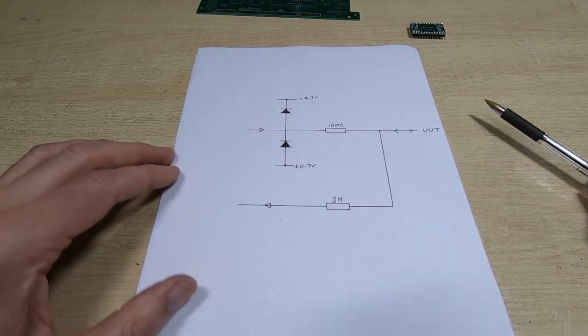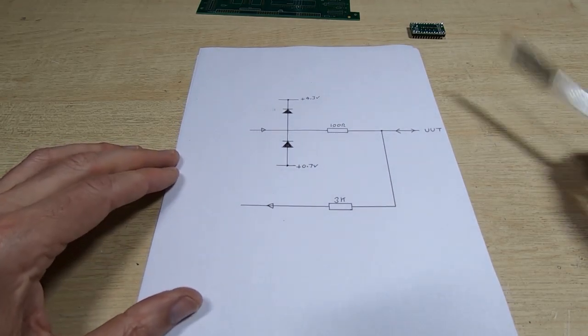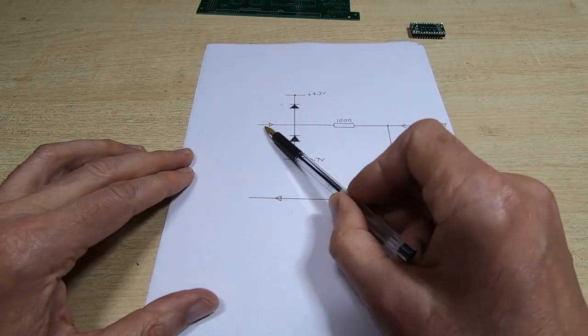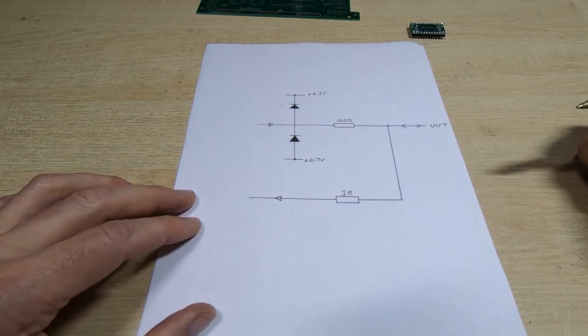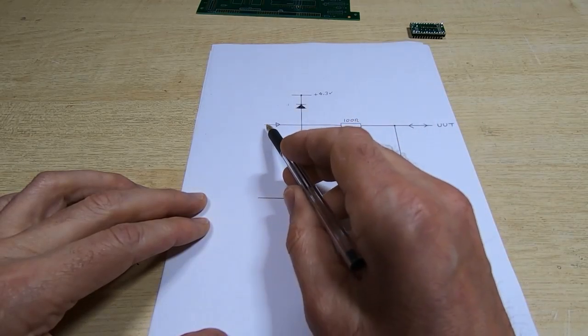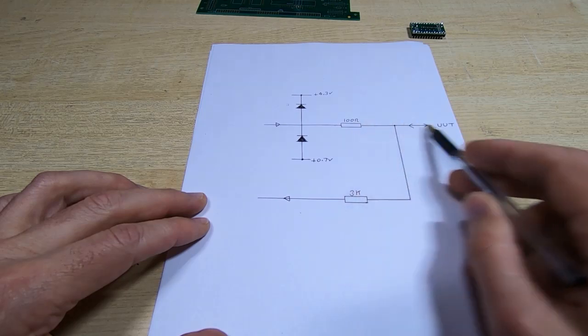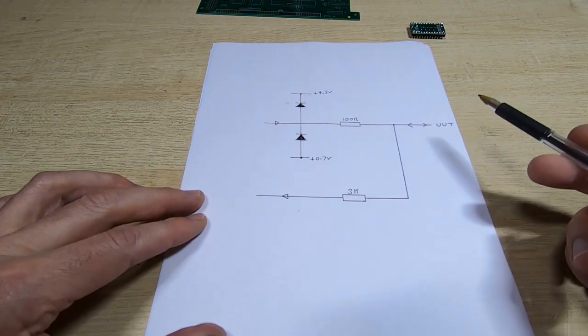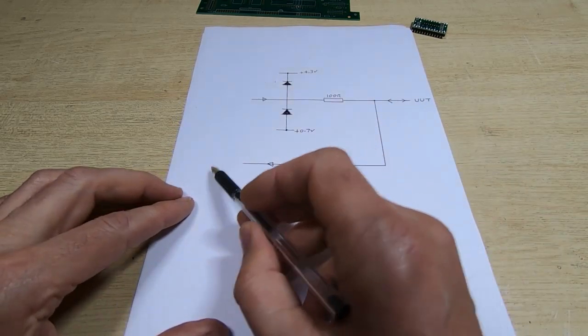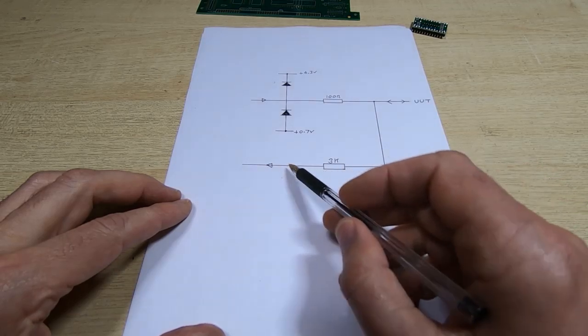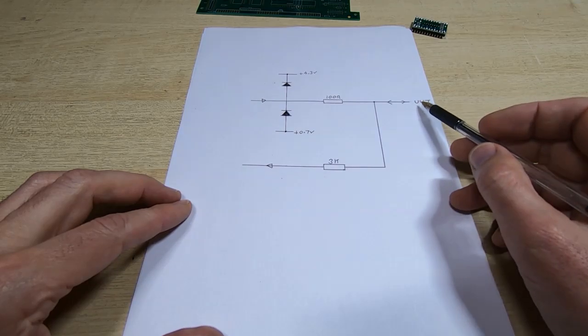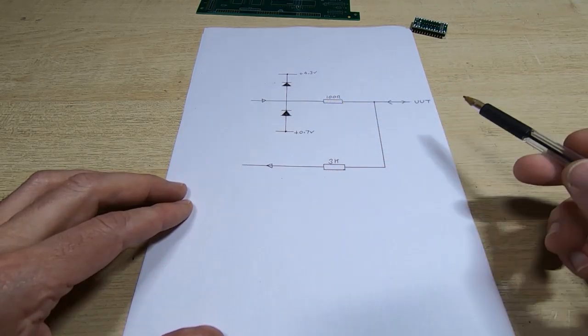Let's look at what's in the protection modules. I've got a CAD drawing here of one channel - there are eight per module. It's an in-out module with a single pin going to the UUT. You have an output from the Fluke pod that goes through a 100 ohm resistor directly out. The protection is just current limiting through the resistor. Coming in, you've got a 3k resistor going to the latches on the pod to isolate the pod and reduce loading on the UUT.